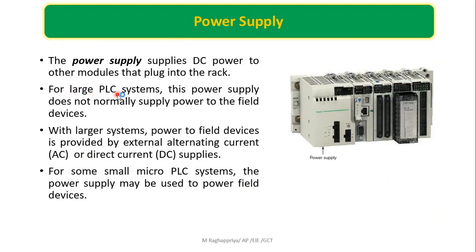In case of larger PLC systems, the power supply will not be provided to the field devices. That is, you have a power supply module here, it will provide supply to the PLC. For a larger PLC system, this will not provide supply to the field devices. Separate power supply for the field devices will be given. But when you go for small micro PLC systems, the power supply is provided to the field devices also.